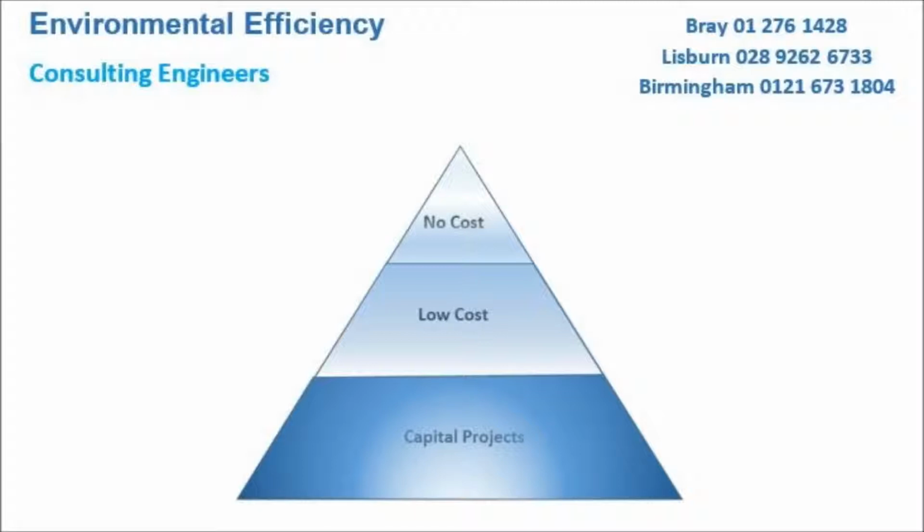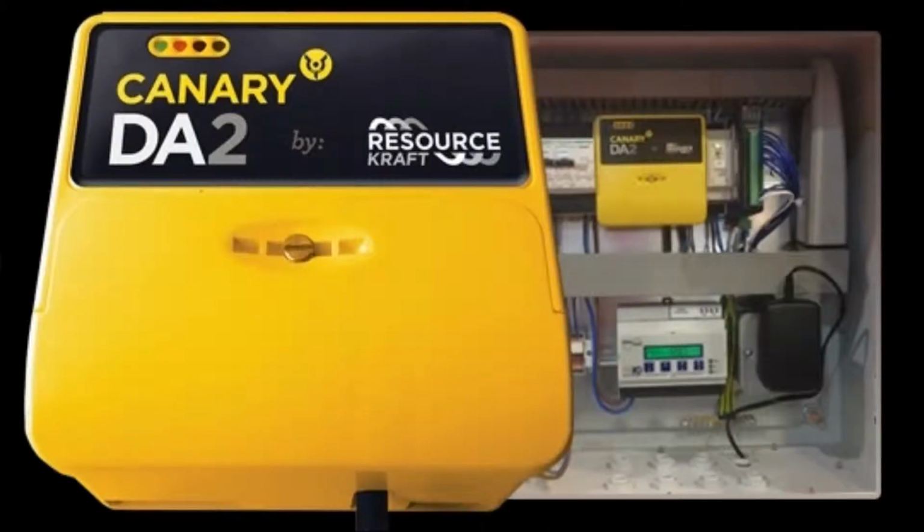The second tier of actions to reduce the carbon footprint involves installation or upgrade of controls. Carbon savings of a further 10% are often realized. Whilst cost saving is not a primary consideration, paybacks of less than 1 year are typical, and thus projects can be easily financed. Such recommendations would include room thermostats, time clocks, occupancy detectors, weather compensation of heating circuits, and data acquisition and control.